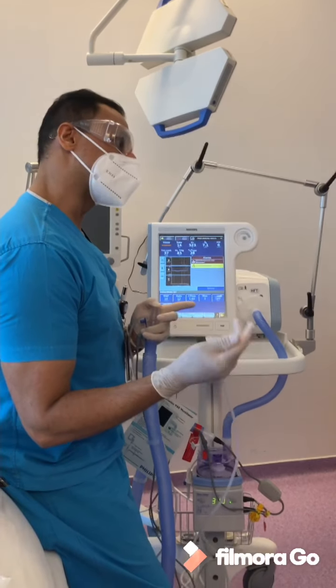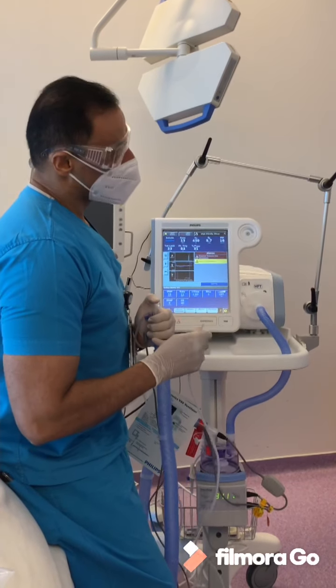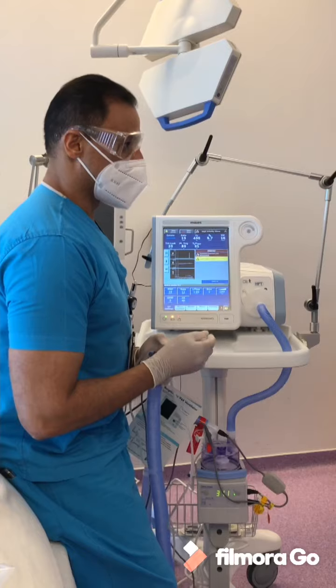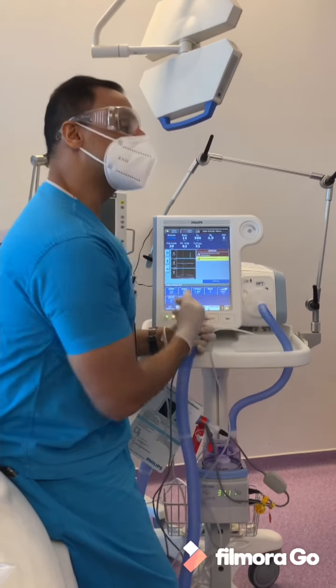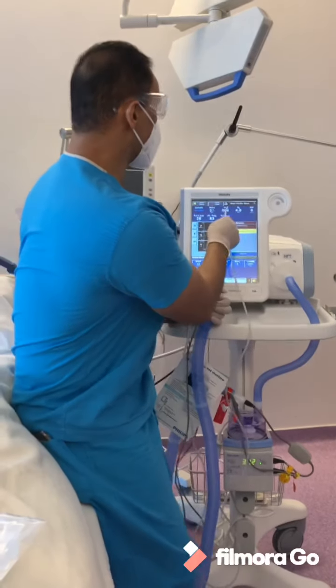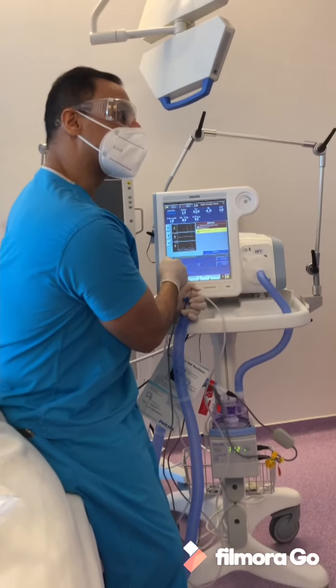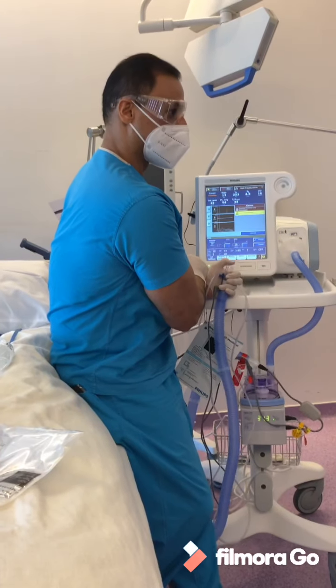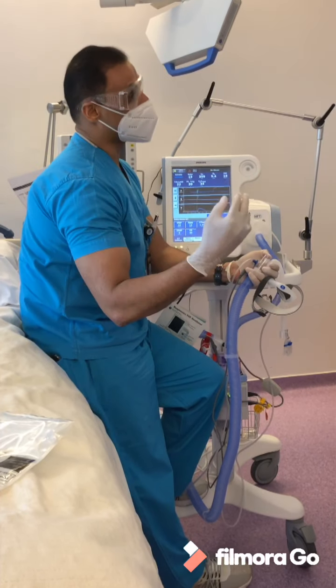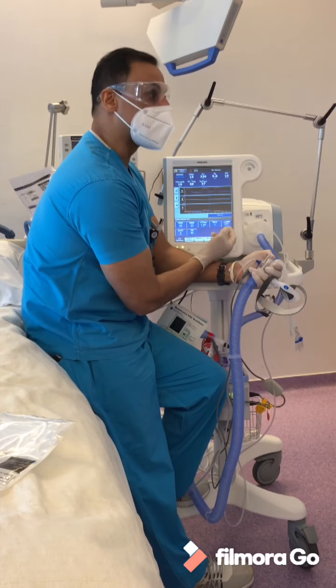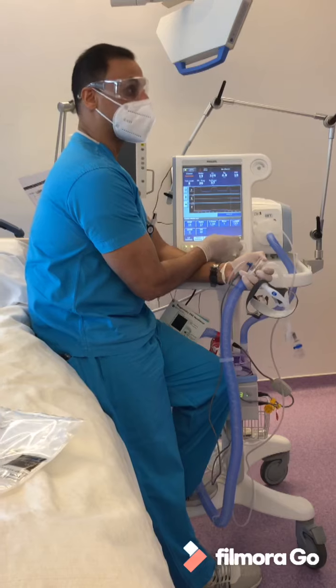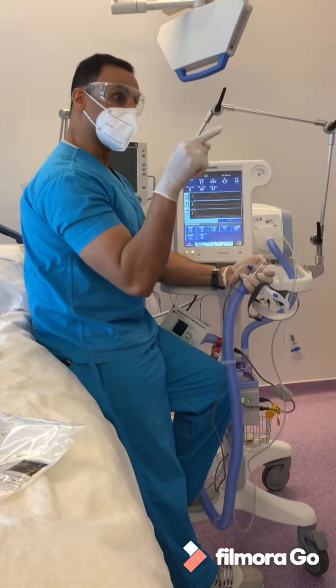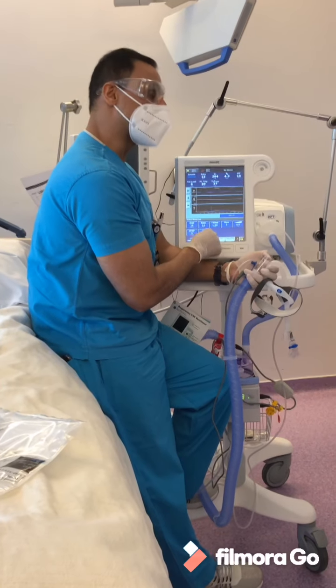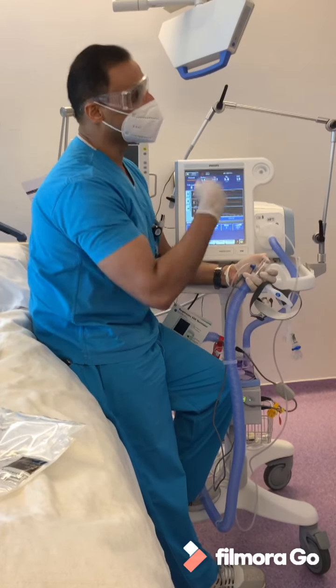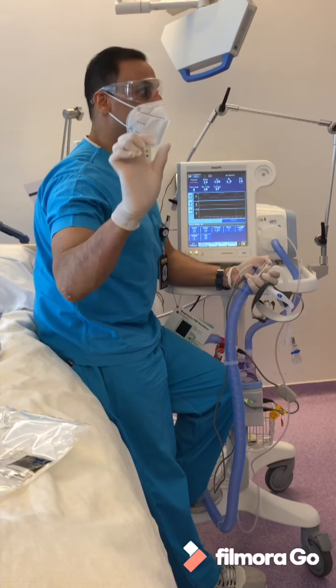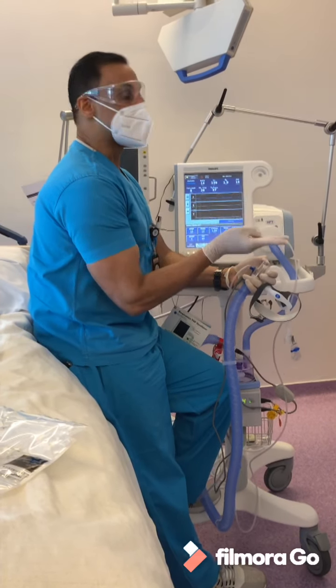Two kinds of alarm, red and yellow. Yellow means not really danger, but you have to take action. It's not really risky to the patient. Red means it's risky, because on this pressure you cannot really know how much pressure you're delivering, here 18, and how much tidal volume you will get. So, from high flow to BiPAP, you have to go to standby. Your main button to change from high flow to BiPAP is standby, and then from BiPAP you also choose standby to go to high flow. So standby is your main button for switching between high flow and BiPAP.